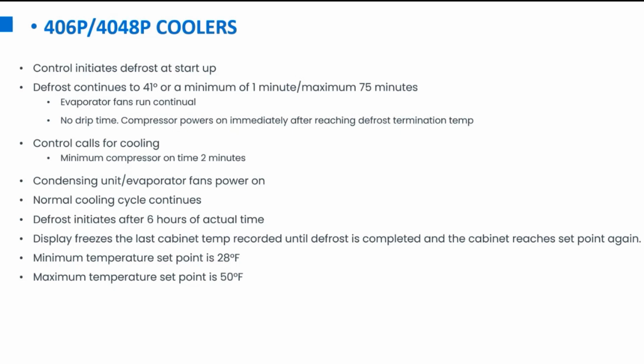Yeah, if you wanted to, with it being on clock time, let's say a customer has their cooler or their freezer going into defrost at an inopportune time of their day. You can explain to them that by unplugging and plugging the unit back in, basically just reestablishing power to the unit, that resets that clock. So when you plug it in, it starts counting down those 6 hours. So if they're having an issue where their cooler is going into defrost mode at, say, noon when they're in their busiest time, you can explain to them to disconnect and reconnect power at, say, 9, 10 o'clock in the morning. That will put their defrost window well beyond their lunchtime, in between lunch and dinner. That way your unit is not entering that defrost mode at your most inopportune times.